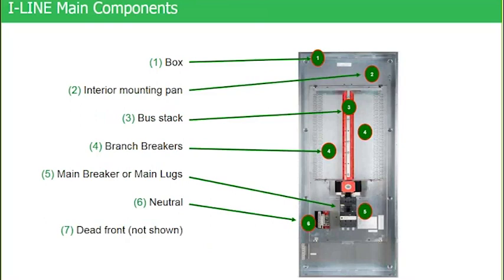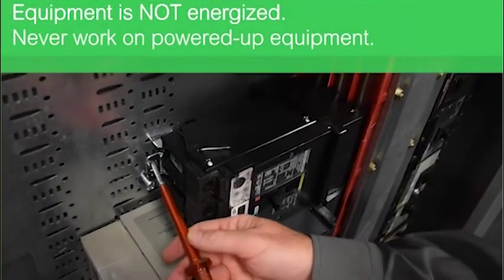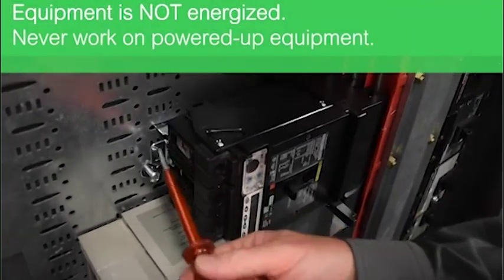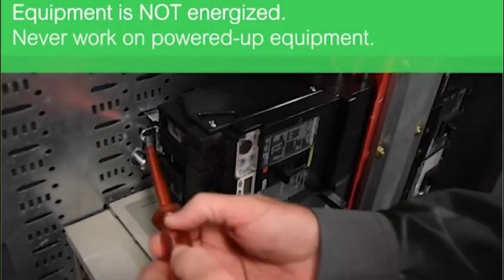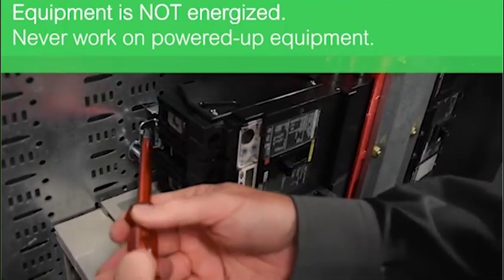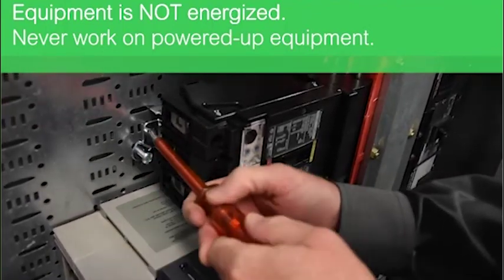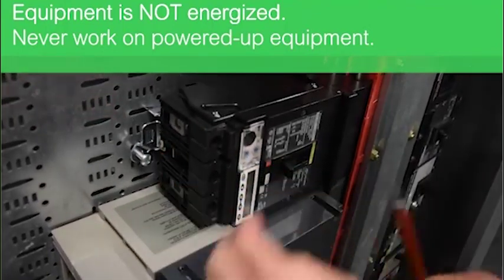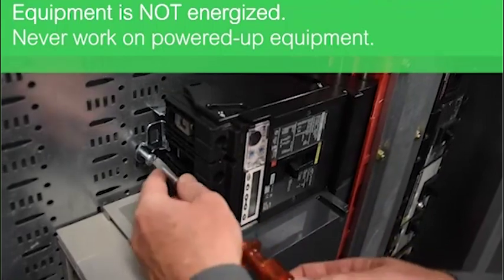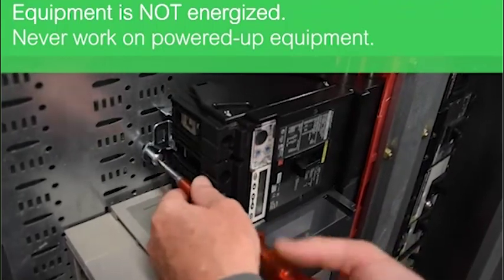Where number four is pointing to, you see some cutouts on the far left and right side of that mounting pan. And that's actually what the breaker ratchets into with that straight blade screwdriver, and then the bolt-on connector that goes into the mounting pan actually bolts into those cutouts.